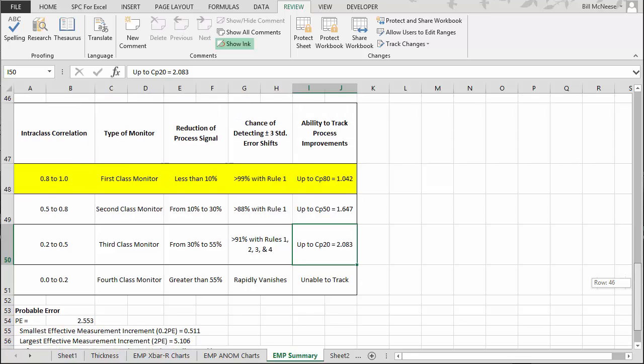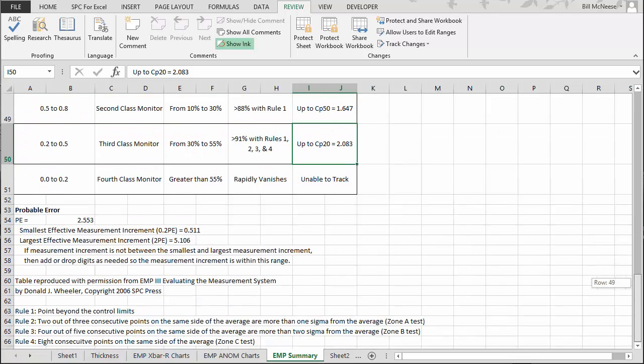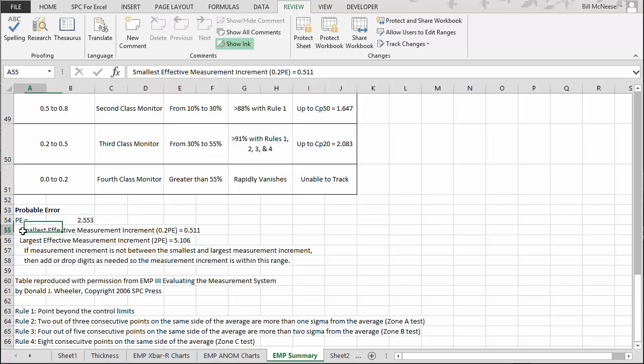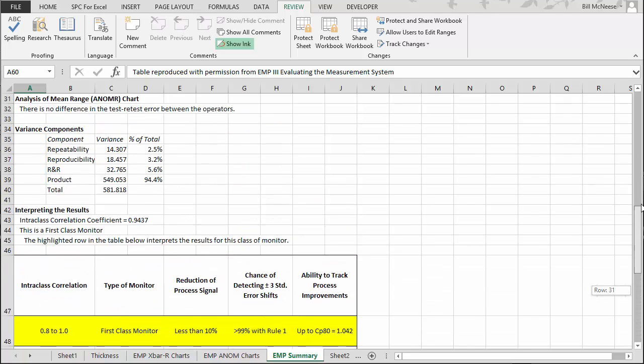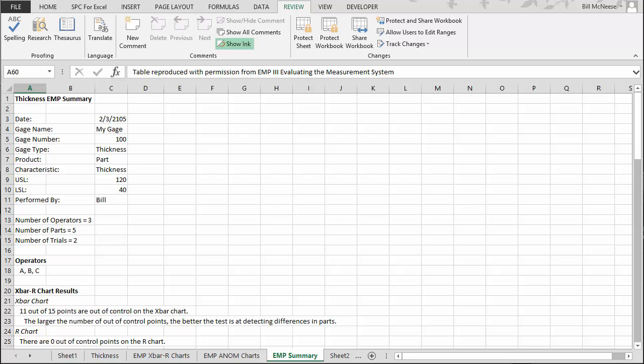The summary table also gives the probable error, which is 2.553. This helps you determine whether you have effective measurement increments — it gives you the smallest and largest effective measurement increment. If your measurement increment is not between those two values, you need to add or drop digits to bring the measurement system within range. This table is reproduced with permission from Dr. Wheeler's book Evaluating the Measurement System, EMP3, and the four detection rules are listed as well.